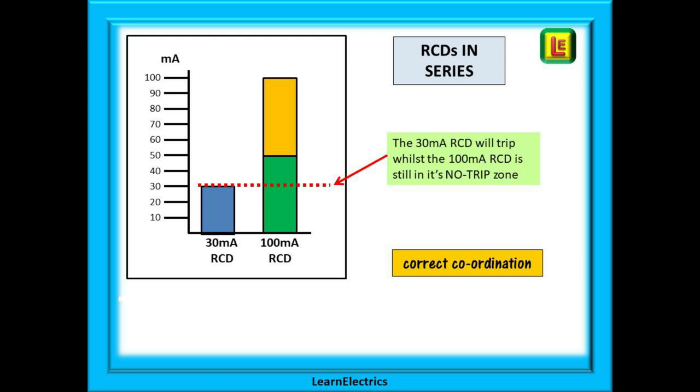If we compare a 30 milliamp RCD to a 100 milliamp device we can see the reason for this 3 to 1 requirement. If these two devices are cascaded together in other words in series and a 30 milliamp fault is detected then only the 30 milliamp device will trip since 30 milliamps is still in the no trip zone for the 100 milliamp RCD.